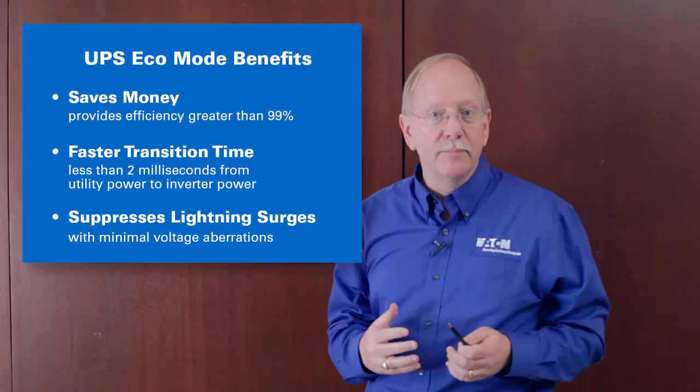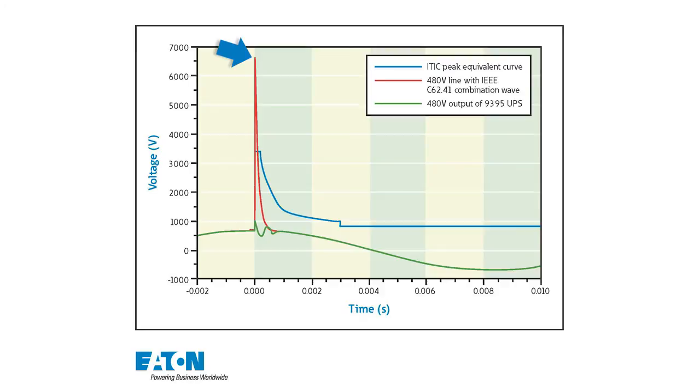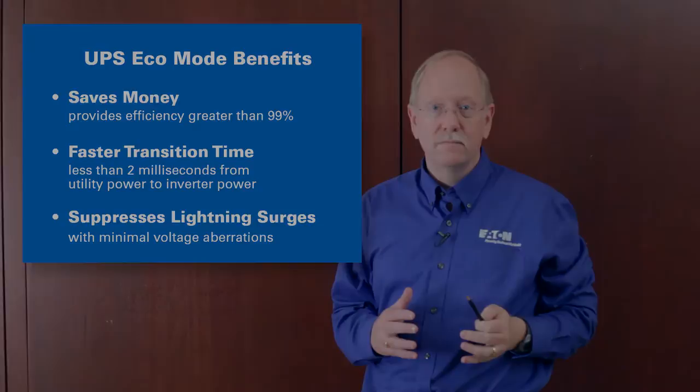One of the primary concerns with eco mode UPS operation is, what if I have a disaster like a lightning strike on the input terminals of the UPS? So, this graphic shows how that would look. I have a 6,500 volt very narrow spike here on the input of the UPS in eco mode, but the green line here shows only a small voltage aberration at the output of the UPS. An eco mode UPS, a good one, can actually suppress lightning strike style surges.